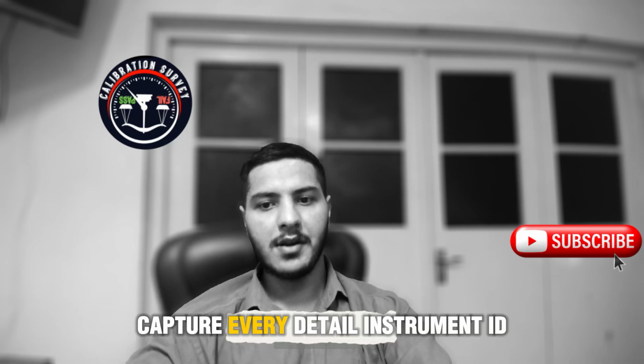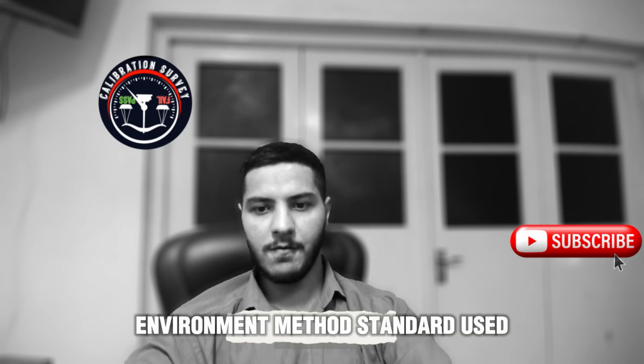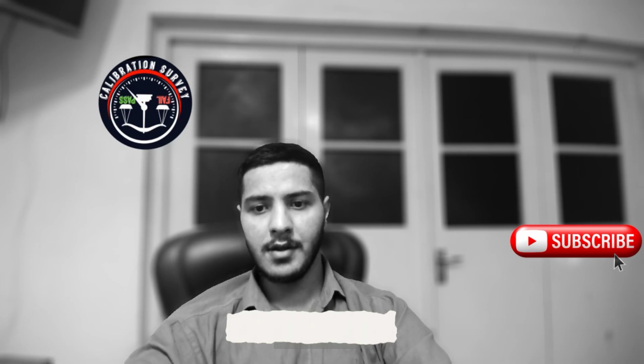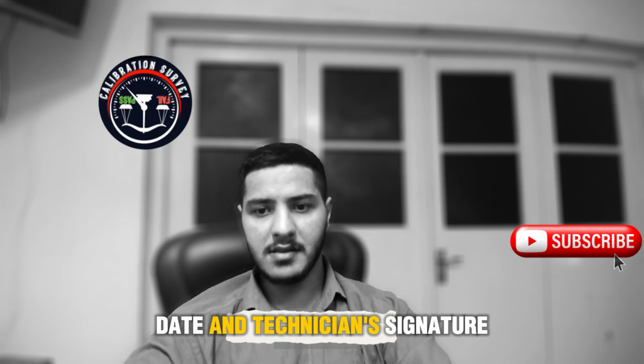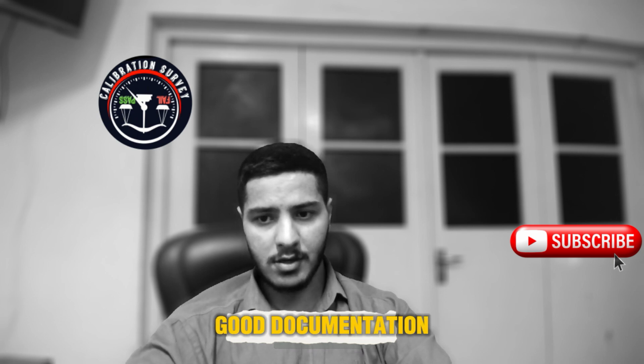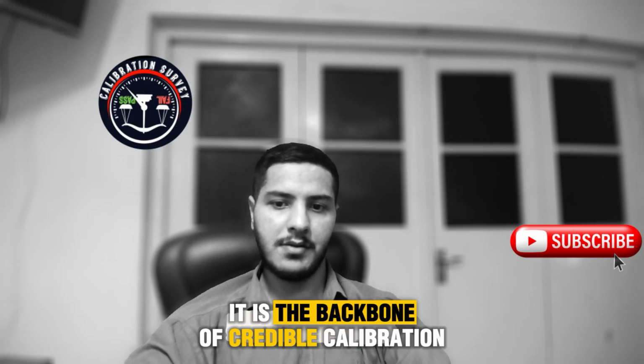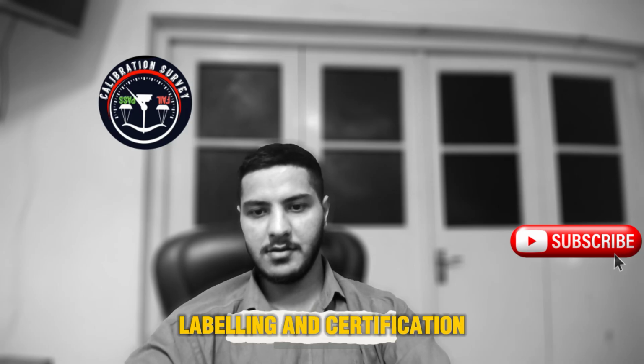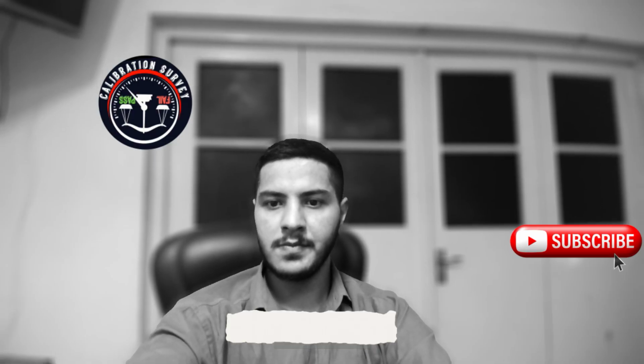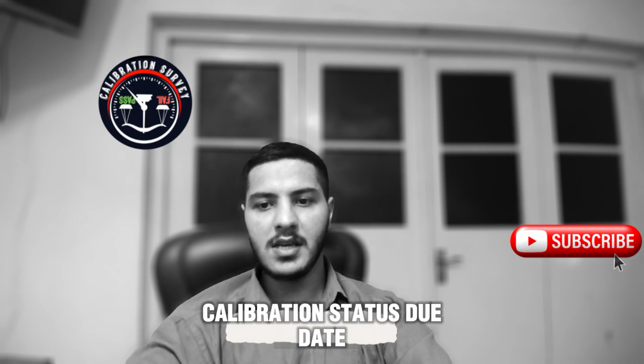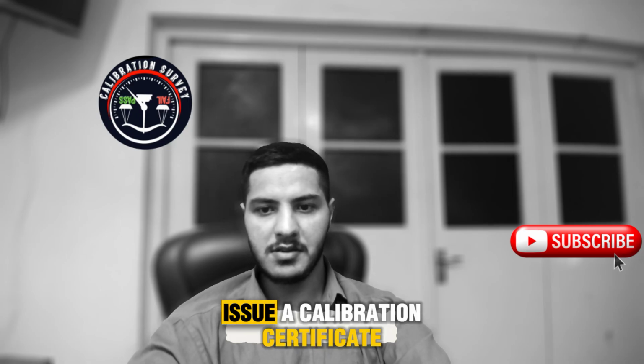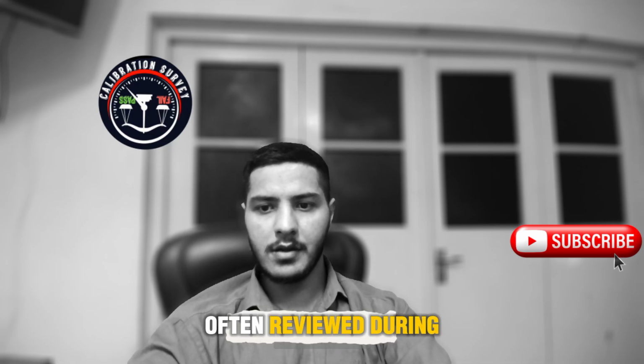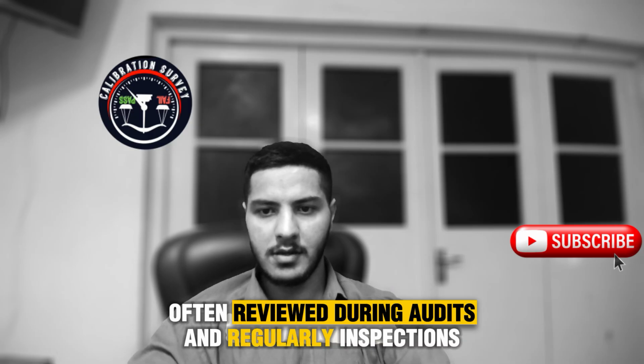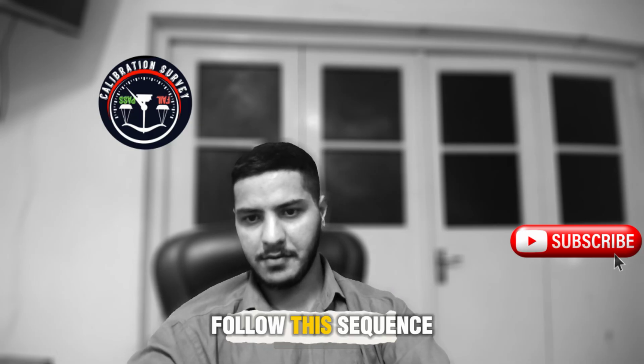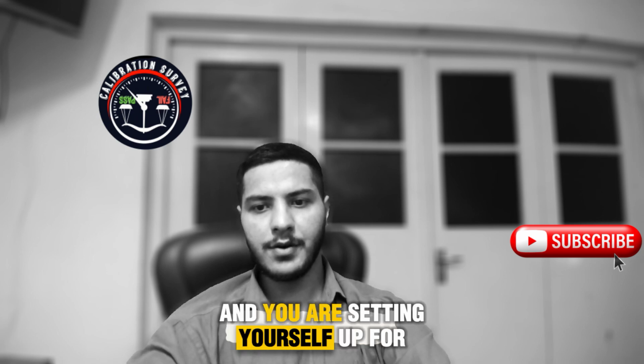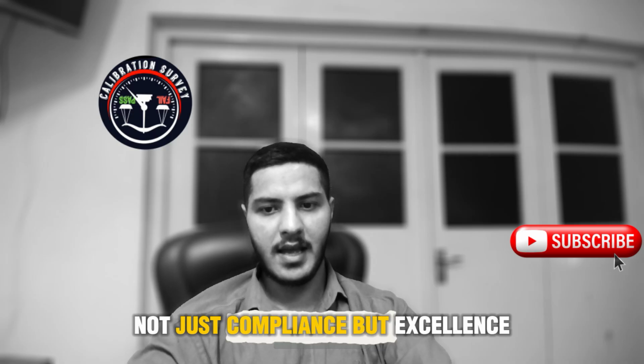Documentation. Capture every detail. Instrument ID, environment, method, standard used, results, uncertainty, date and technician's signature. Good documentation is the backbone of credible calibration. Labeling and certification. Mark your instrument's calibration status and due date. Issue a calibration certificate, often reviewed during audits and regulatory inspections. Follow this sequence, and you are setting yourself up for not just compliance but excellence.